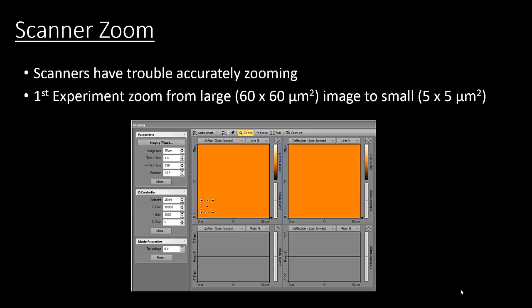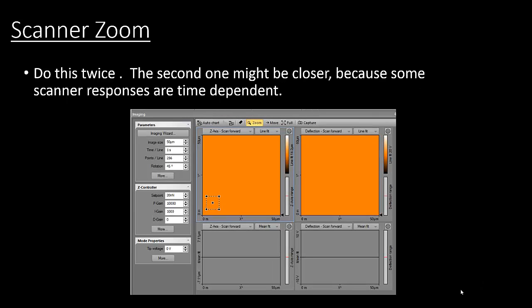Part 1. Scanner head calibration. Most scanners have trouble zooming properly. In this first exercise, you'll zoom from a large 60 micron scan to a small 5 micron scan. When choosing an area to zoom, choose a spot off-center. You will do this twice. This is because of the time dependencies of the zoom head. Usually, the second zoom is more accurate. A good example of a zoom choice can be seen below.